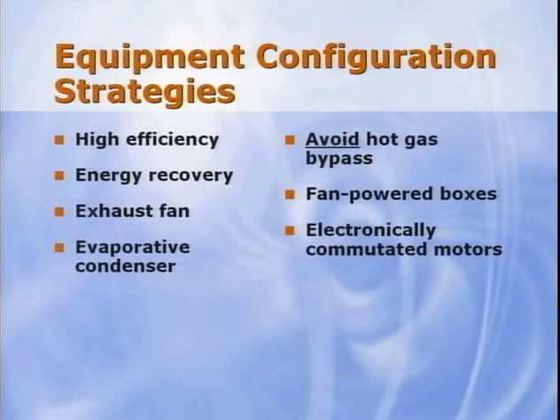Okay, so far the team has focused only on the equipment. All of the discussed strategies can be added to systems to help reduce system energy use. Remember that hot gas bypass is something we want to eliminate, if possible, since it is so inefficient. Next, on to alternative system designs. First up is Paul with single-zone VAV.